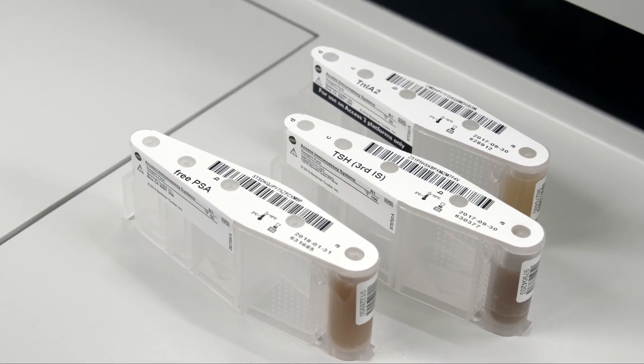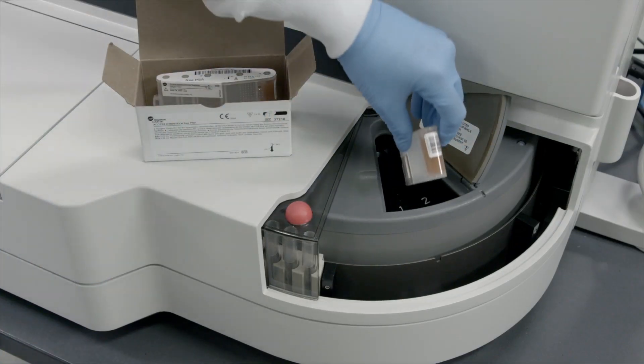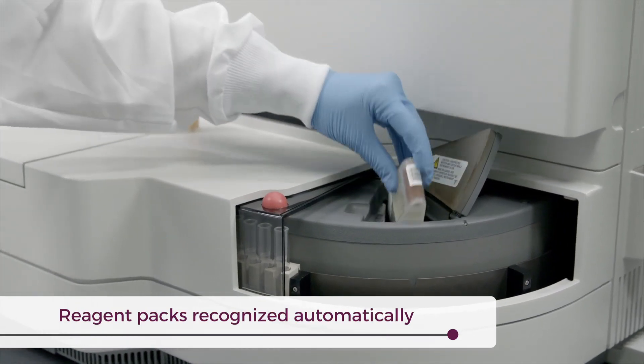The ACCESS-2 features liquid, ready-to-use single-pack reagents, which go from box to system with ease. Operators can load multiple reagent packs, while the system automatically detects and identifies packs during loading and unloading, preventing operators from loading the incorrect reagent pack into a slot.